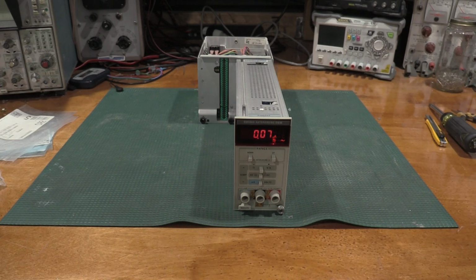Given that we've tested the ranges and things like that, this meter is measuring quite well and is ready to go back into service. And I can get this back to its owner. I'm going to talk to them, and at the moment I'm going to advise not to mess with the calibration. It validated very, very well, and I don't think we can improve it much more. So in this case, my personal opinion is that it would be better to let calibration constants stay constant, and to not enter cal mode and blow out the EEPROM. Again, not my unit, so that's totally up to the customer. We'll see what they say. But for right now, I think this one's good to go and ready to head back to its home.